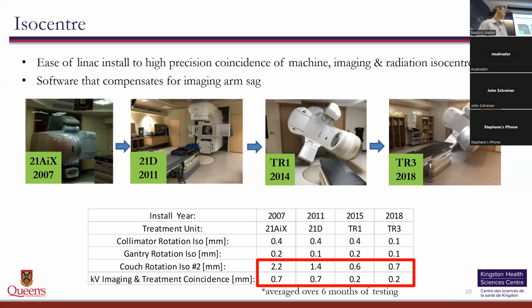The couch, I don't know if you can see in the bottom corner, I've highlighted in red, but one of the initial ones that I talked to you about, our couch rotation was on the order of about 2 millimeter slop. That means as you rotate around, it would not hold a perfect circle. It would slop by about 2 millimeters. We're all the way down to about 0.7 millimeters, and all the rotations are anywhere between 0.1 and 0.2 millimeters for a massively heavy machine spinning around a patient. This allows us to precisely target where we are hitting things.